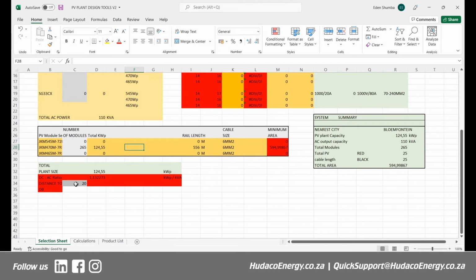If you have estimated here the distance to your DB to about 20 meters, we have added an allowance of 5 meters to say if your estimation was not so accurate, you still have some 5 meters or so to play around with for your PV cables. So that will be your distance from your panels to your DB.